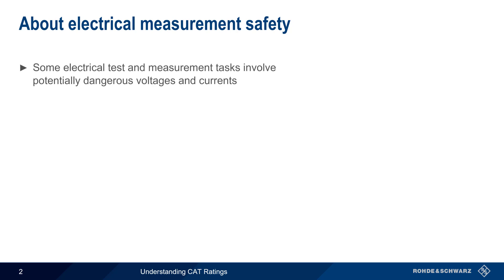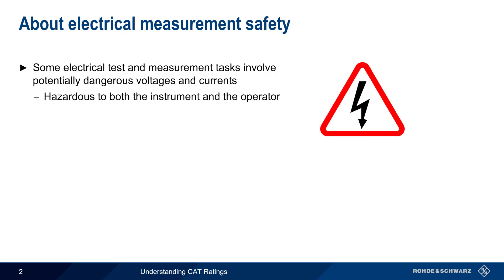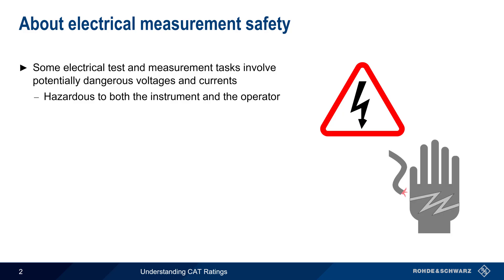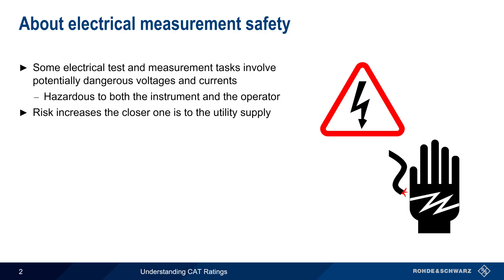Some electrical tests and measurement tasks involve potentially dangerous voltages and currents. Dangerous refers both to the risk of damage to the instrument, as well as the risk of operator injury or even death. This risk increases the closer one gets to the voltage source or utility supply. Shorter distances mean lower impedance between the measurement point and the voltage source, and hence the potential for higher currents.